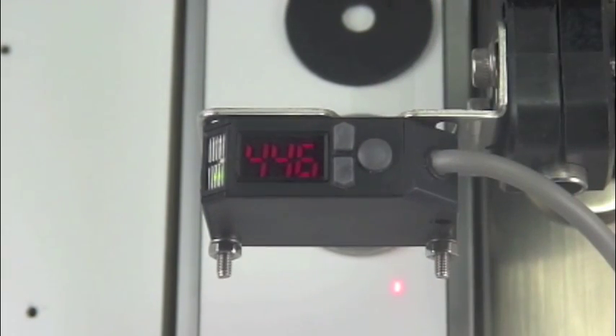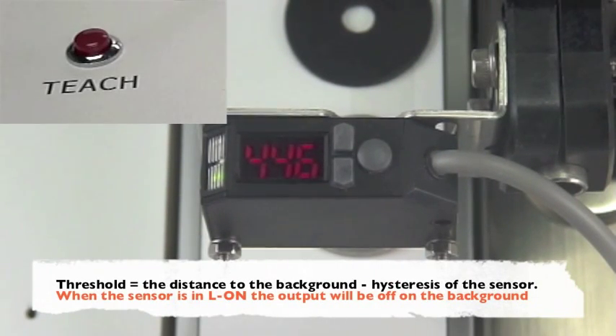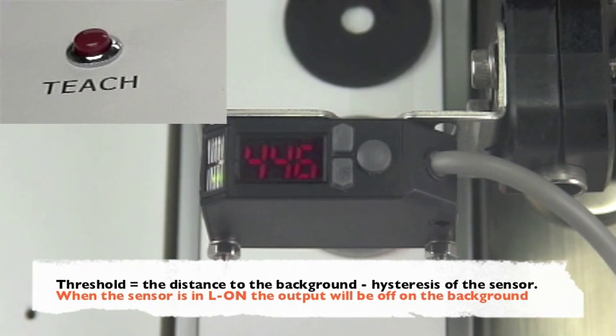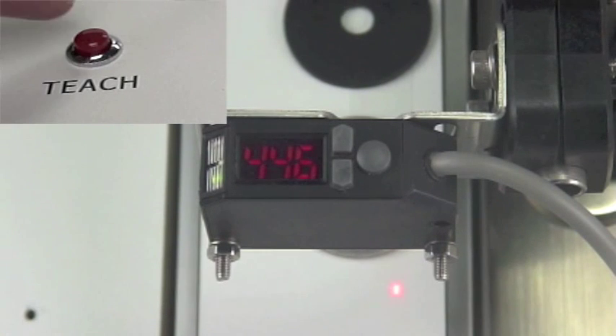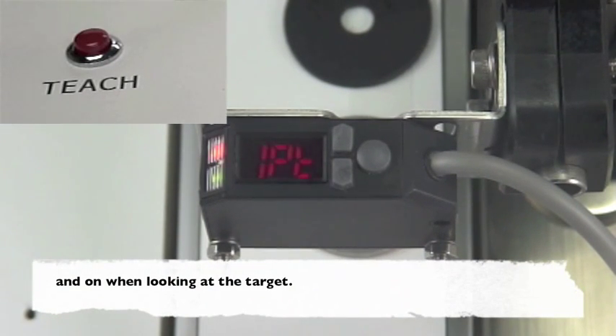With the sensor positioned looking at the background, I press and release the teach button. The threshold is automatically set to the distance to the background minus the hysteresis of the sensor.